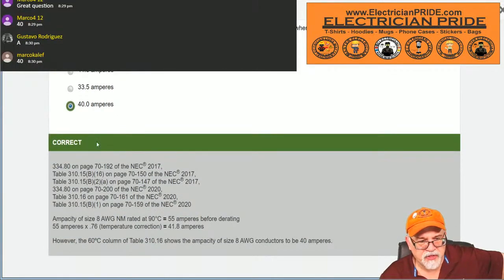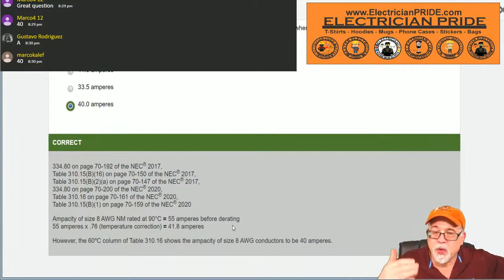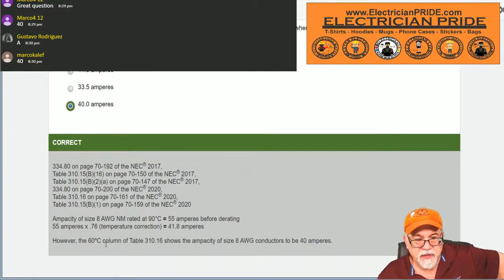Now, this is a lot of chain of thoughts here. But you see right here, 8 AWG, rated 90 degrees C. I wish they had put the dash B, but it's okay. I guess that's where they're getting it. It's 55 amps times 0.76. Because of that insulation rated 90, it was 41.8. But remember what the rules said? 60-degree column, table 310.16 shows the ampacity of an 8 as 40 amperes.